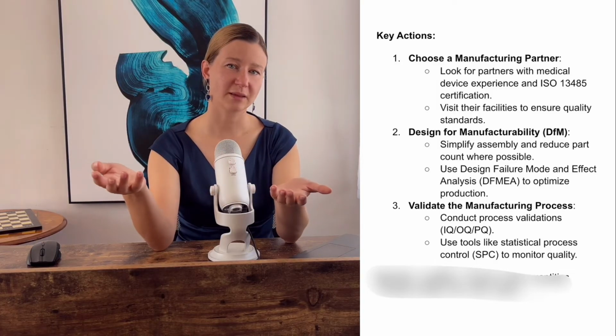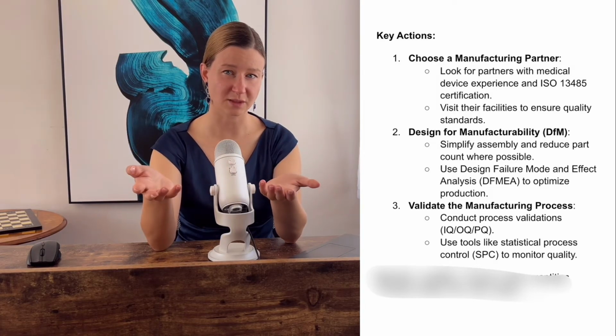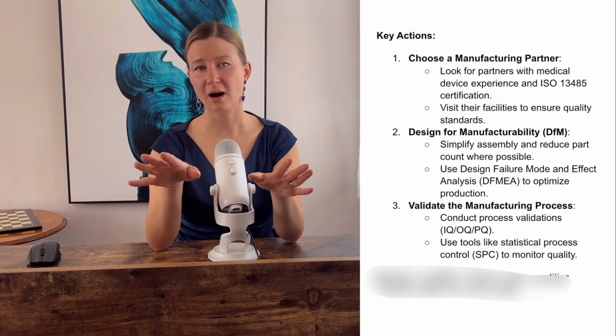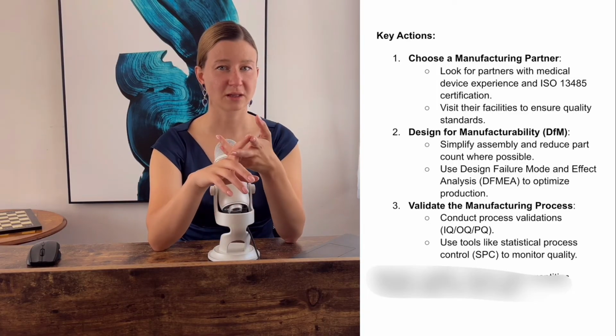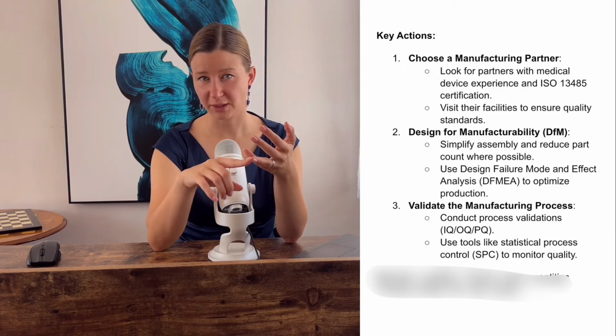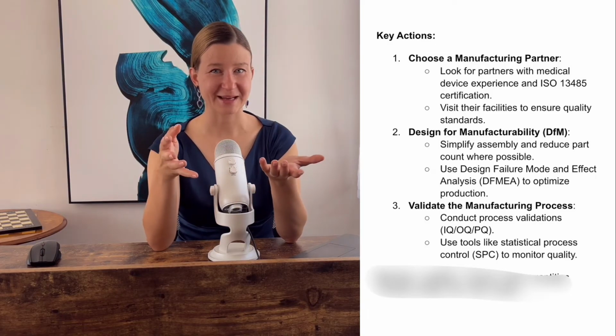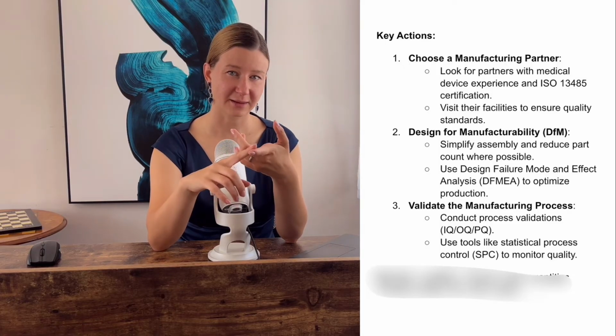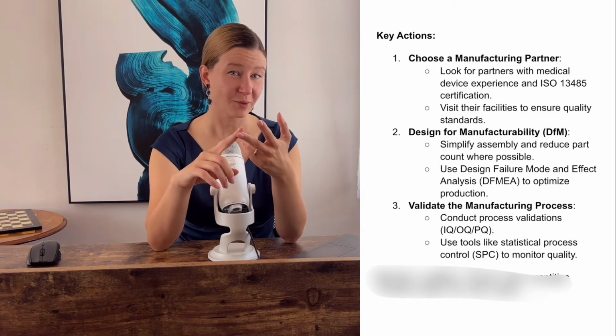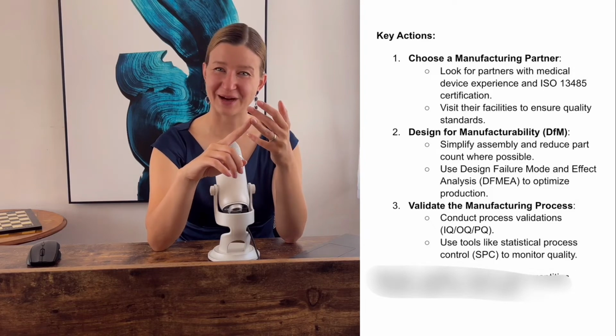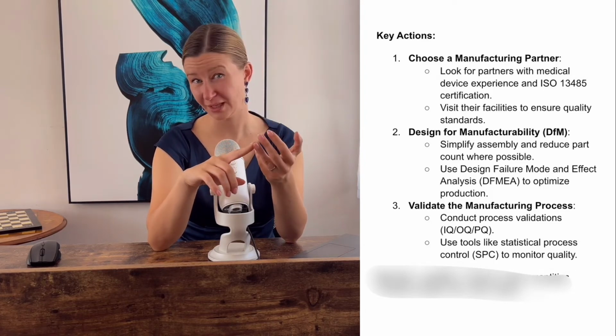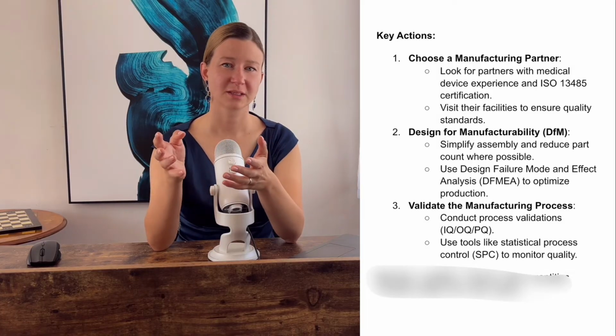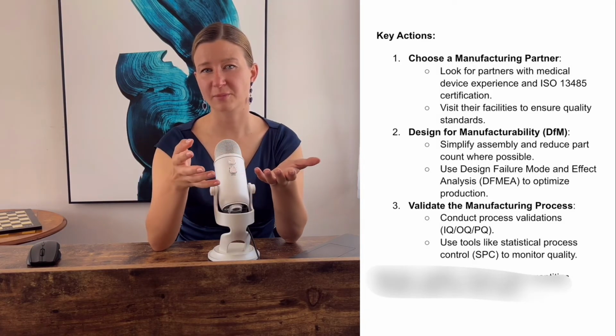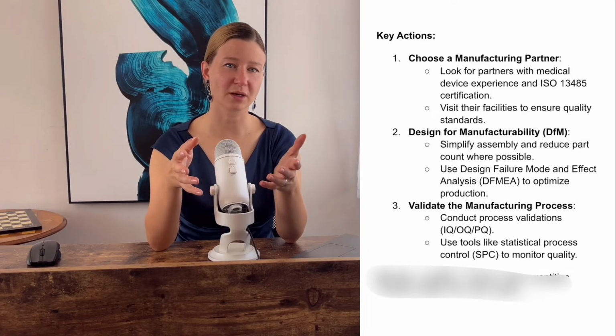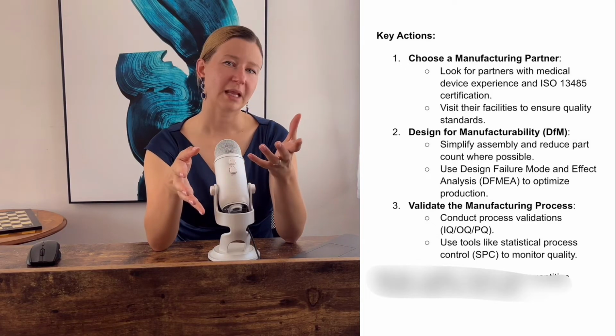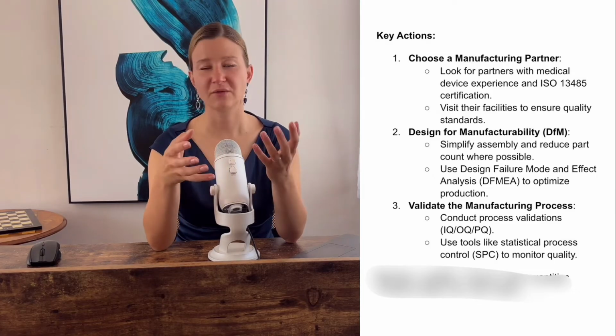Once you're ready to start making the device, you need to test the production process. There are 3 key steps for this: installation qualification, operational qualification, and performance qualification. Now, these are fancy ways of saying you need to test if machines are set up correctly, IQ, if machines work the way they're supposed to, OQ, and if the final products meet your standards every time, PQ. During this stage, use something called statistical process control to track how well the production is going. It helps you spot any problems early, like if a machine is making mistakes or a batch doesn't meet quality standards, so you can figure it out right away.